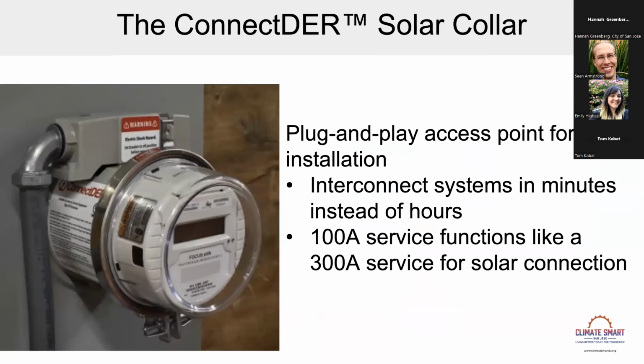So for solar arrays, you saw at the top how solar arrays frequently trigger larger services. That's because technically on a panel, you're not supposed to put more than 16% of power back into it. So on a 100 amp panel, that means 16 amps is what you're allowed to put in through AC electricity. Up on the roof, that equates to a 3.8 kilowatt solar array AC after it's been converted from DC.